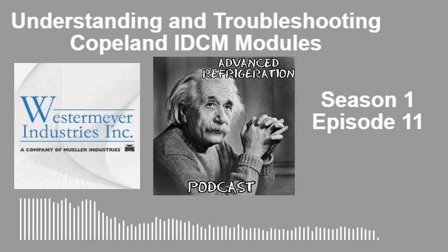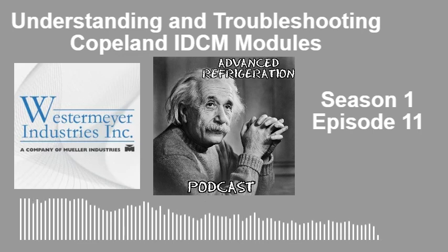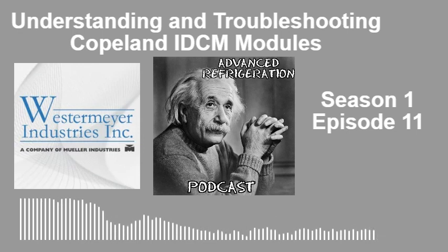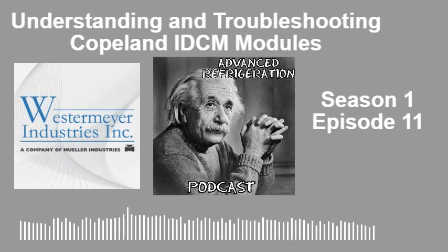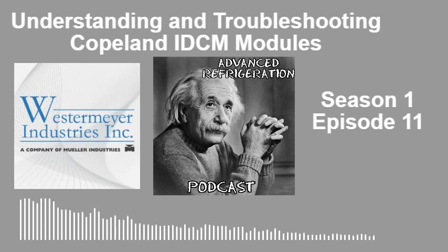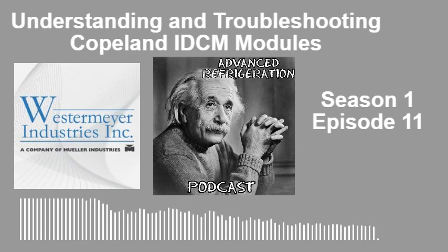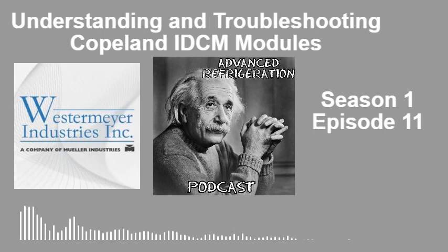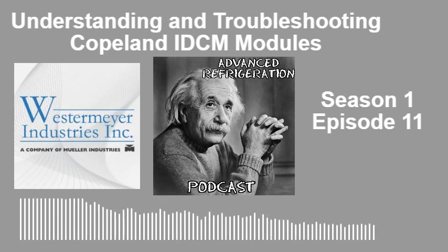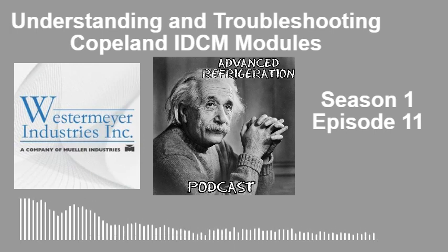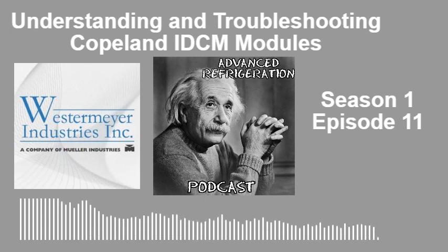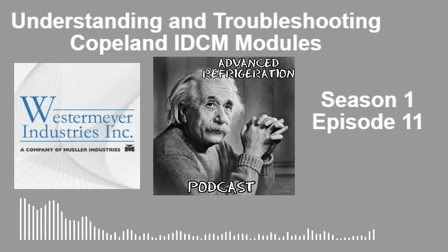But one thing I really want to go over, I want to stress this on these IDCM controllers. They're good controllers, but you need to really follow the instructions when you're doing them. And I'm going to go over a situation that we had, and this was like a massive issue. So I was at a company for a while. They had this one particular customer, big national customer, and digital compressors and their protocols, digital compressors in each rack. So I'm going around all these stores and all these digital compressors aren't working. None of them. Like half of them from a certain date code, these protocols aren't working. And their compressor protector trip.